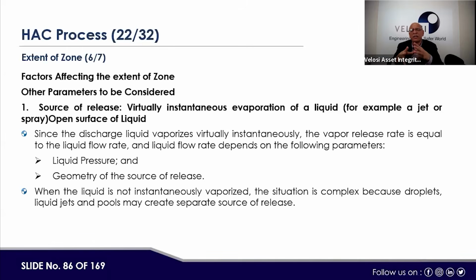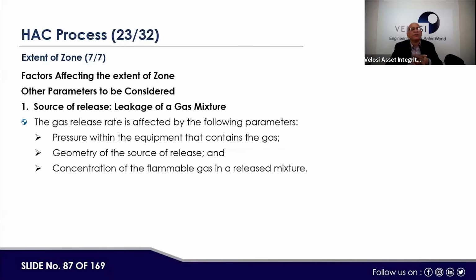But in general, it is easy to follow. There are typical examples available in IP-15 or API 505. Those can be followed to make the zoning for those particular infrastructures. Similarly, for a source of release from leakage of a gas mixture, the gas release is affected by the following parameters: pressure within the equipment, geometry of the source of release, and concentration of the flammable gas.